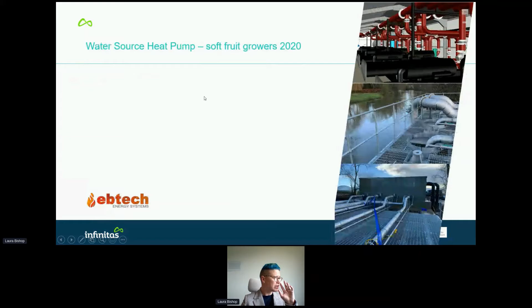The second example is at the other end of the scale: an 8.8 megawatt thermal water source heat pump for a soft fruit growing partnership, designed and installed by Ebtech, one of our members. They deliver strawberry crops to Marks and Spencer's. This system takes about 640 litres a second of water from the river. You can see in the photos the intake chambers and a 3D model of the heat pumps. It's very industrial.